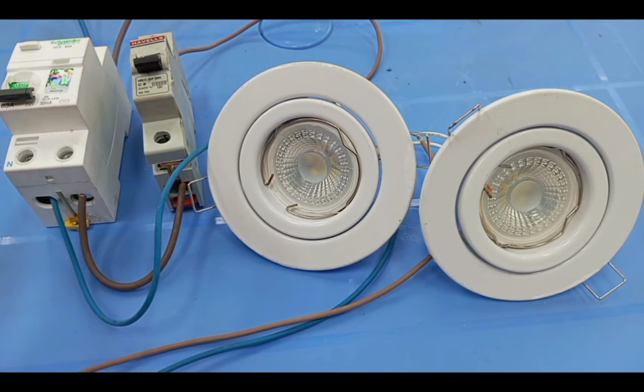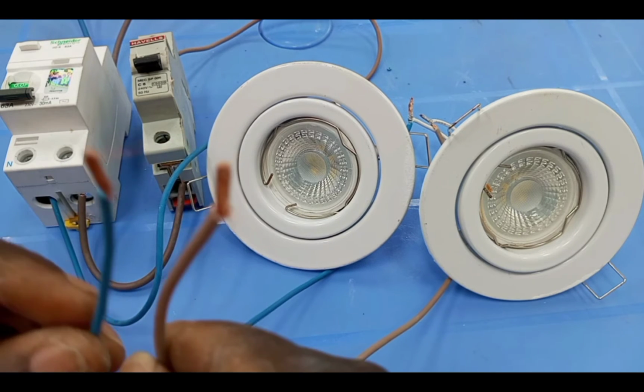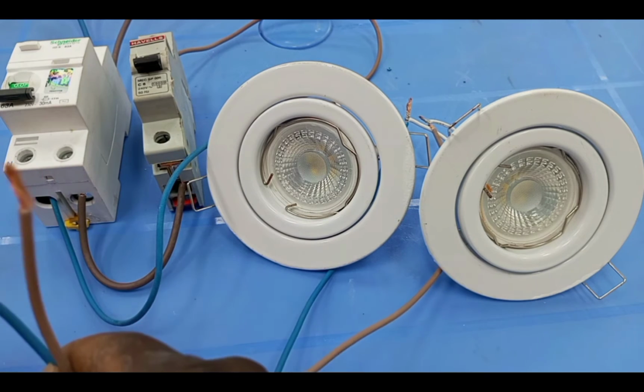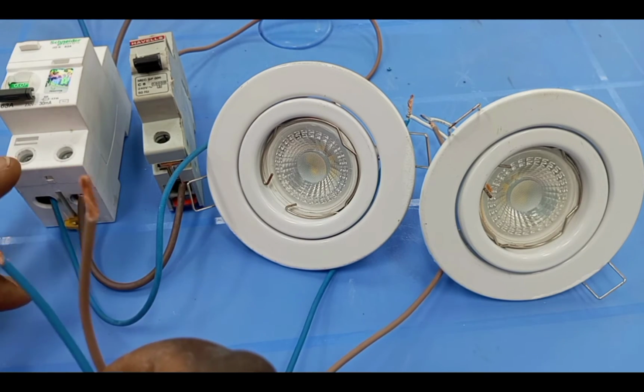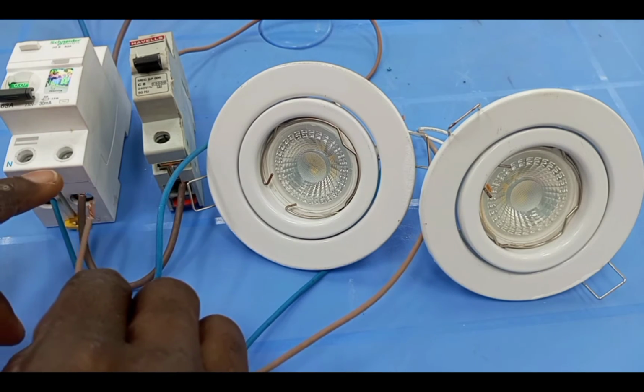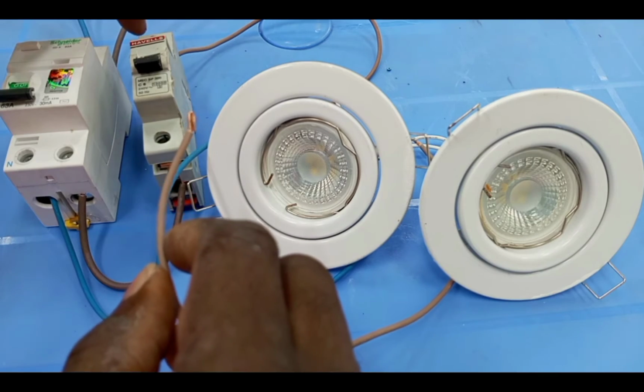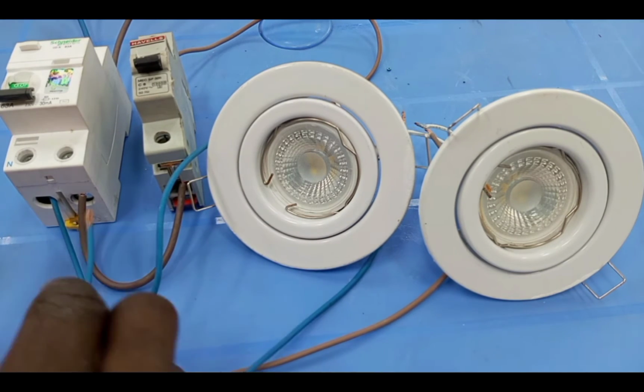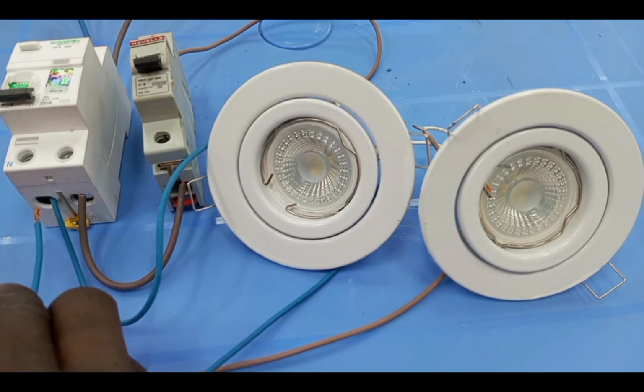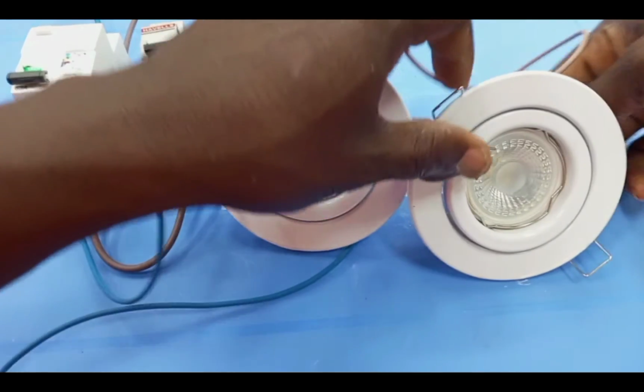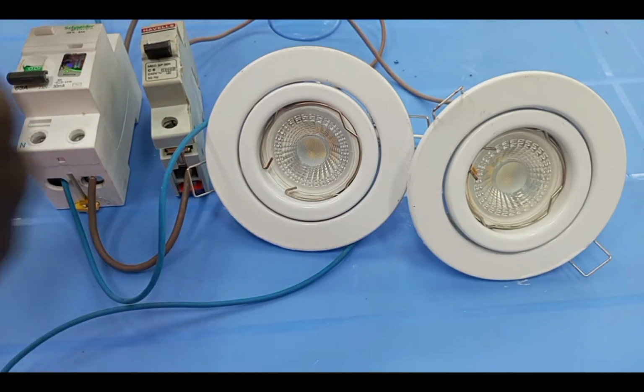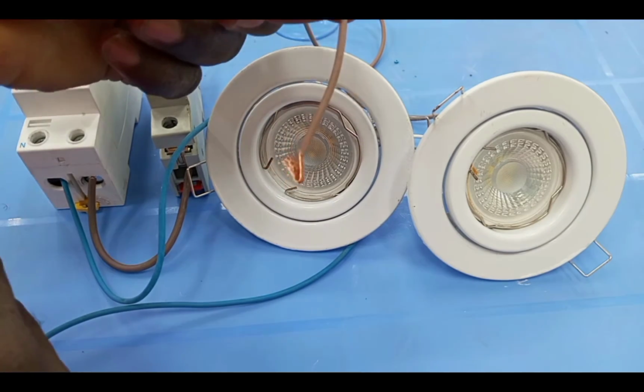Because I have this RCD in the circuit, I have to make sure that the cables to my load are connected from the output of the RCD. That's live from the output of the RCD, in this case, through the miniature circuit breaker. And then neutral must also be connected at the output. So here, because we need short circuit and overload protection, I'll connect this live through the miniature circuit breaker.